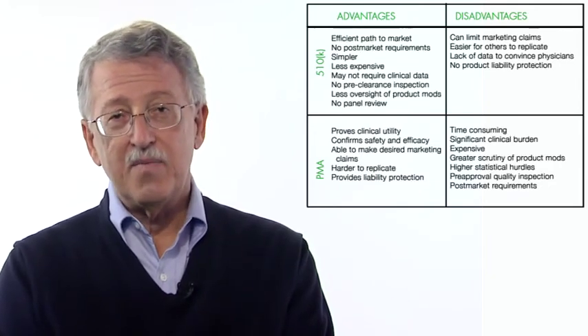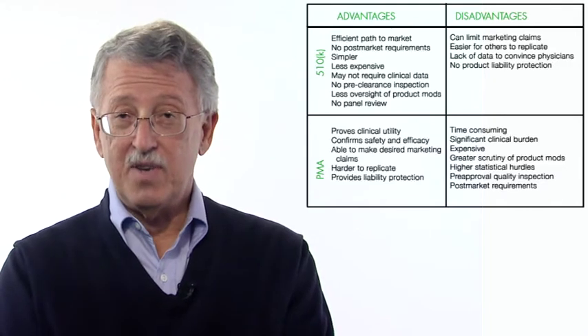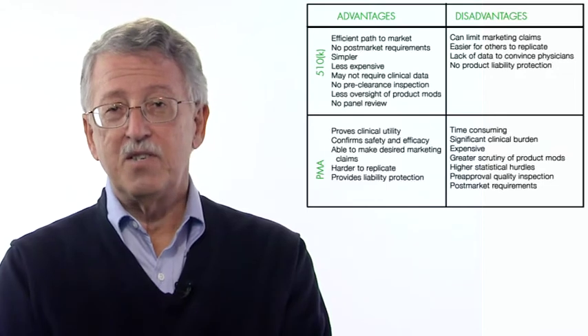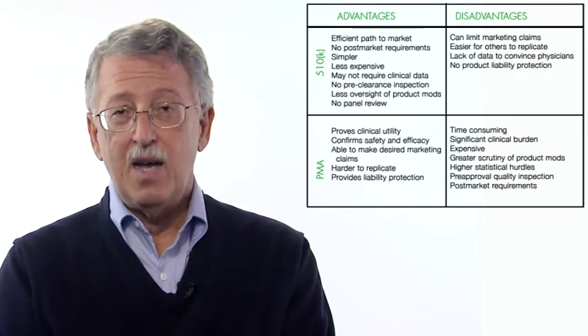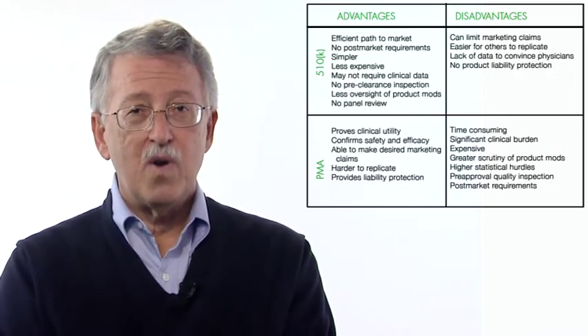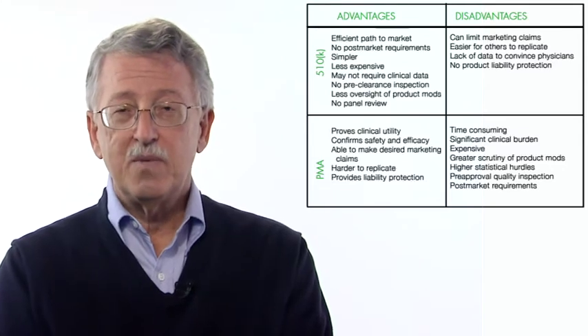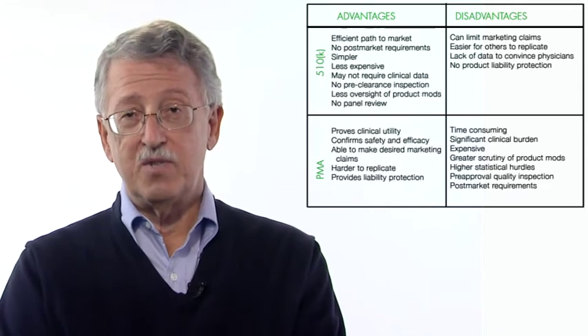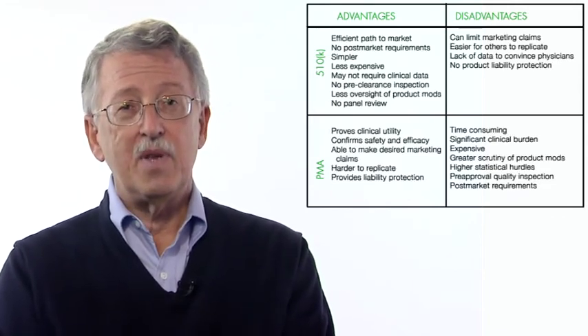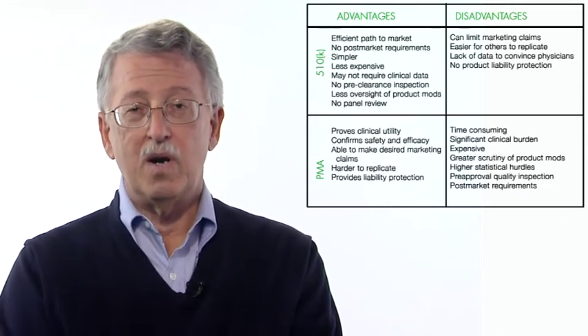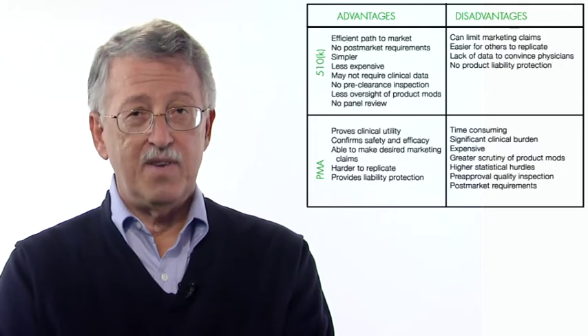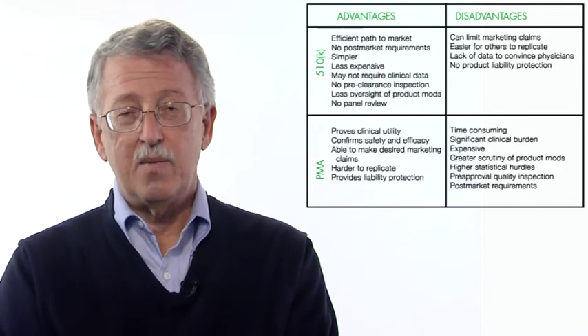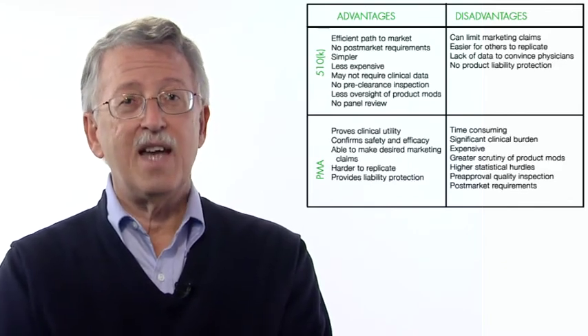On the other hand, the PMA takes a longer time to get through the FDA. It usually requires a bigger study. Application fees are higher. The type of requirements when you're changing the product are more rigorous for a PMA. The type of data and information that goes into a PMA is significantly more than what's required for a 510K. Higher statistical hurdles, for example, more information about preclinical information, things of that sort.